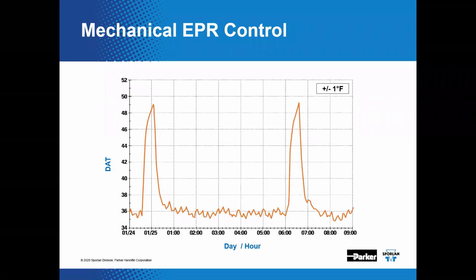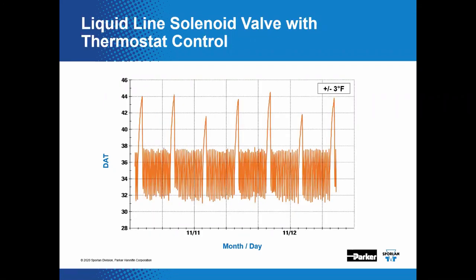Right. Now, we started this series of discussions off with the liquid line solenoid valve and thermostat as controlling devices. And you can see here there's quite a bit of fluctuation in this technique, plus or minus 3 degrees. Varies a significant amount. If you're satisfied, though, with this level of accuracy and it works in your store or your facility, it may be perfectly acceptable. It works. It's just an interesting comparison. You have options. You pay your money and you take your pick.